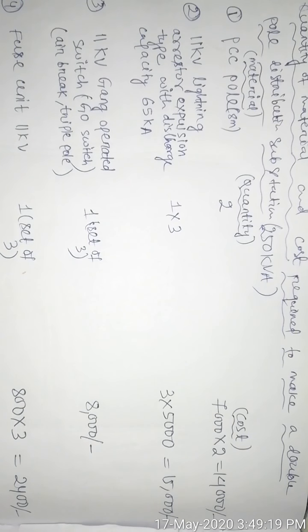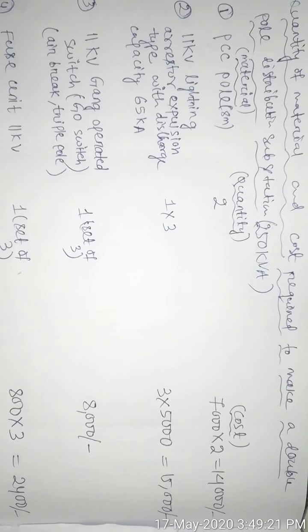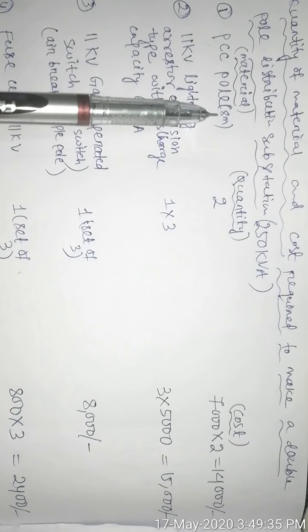So today we will explain the quantity of material and cost required to make a double pole distribution substation which will use a 250 kVA transformer. The first material is a PCC pole, plain cement concrete pole, which is an 8-meter long pole. We require two such poles. As an individual pole costs 7,000, a total of 14,000 needs to be invested in the PCC poles.